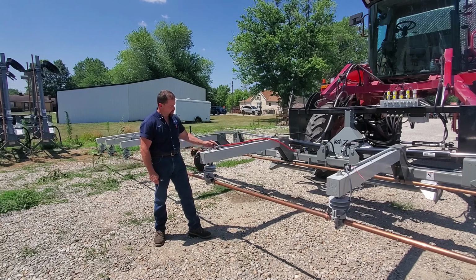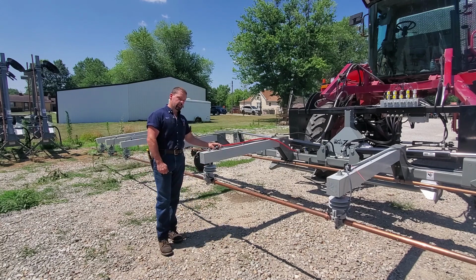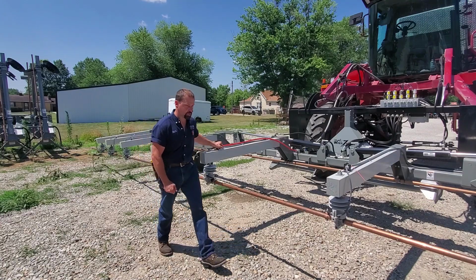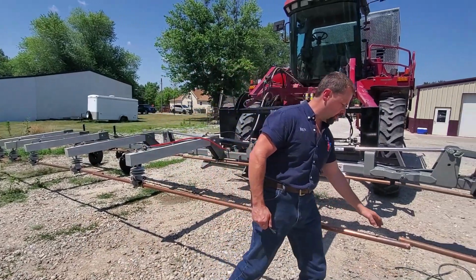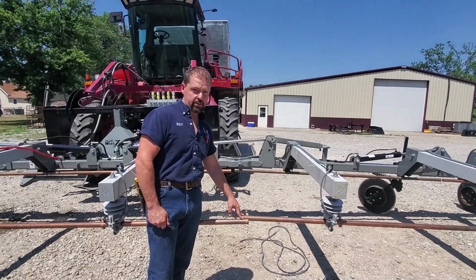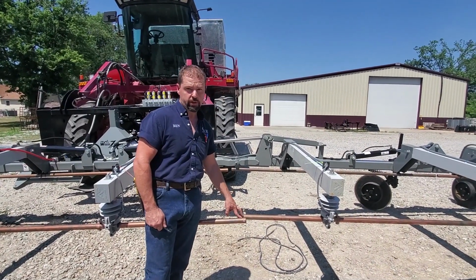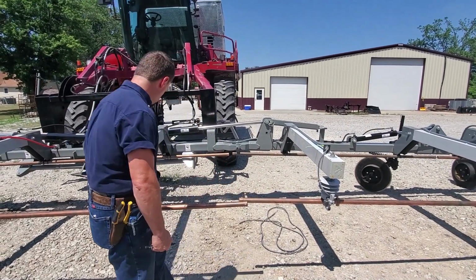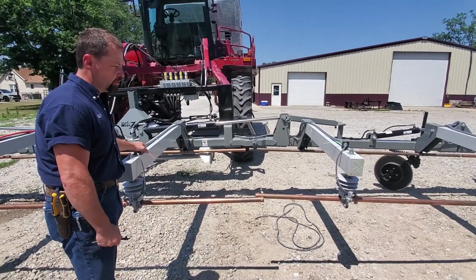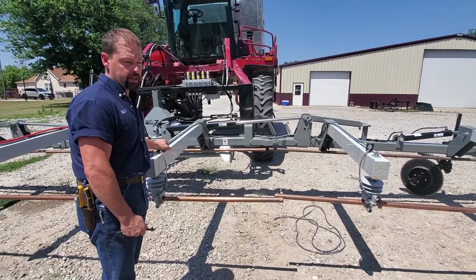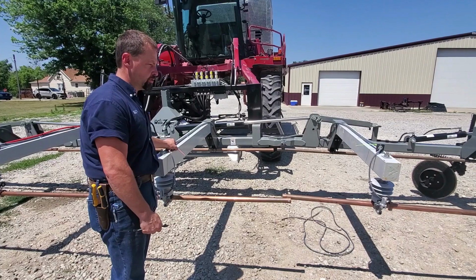So we have to unhook all of our wing wires, and you'll notice how close our hinge points or our pipes are. 15,000 volts will jump between these two points. So you cannot unhook only one side of the cable, you have to unhook both. Otherwise you can still get that false trigger.